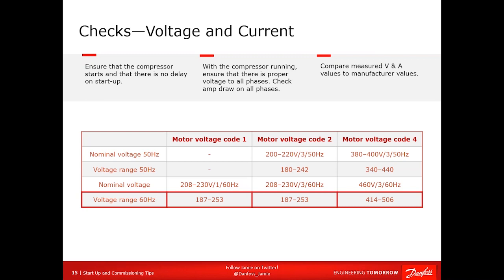So voltage. You have a voltage range and rating. It's in the application guide. That's where this comes from, inside the installation guides as well. And you'll see a range for the voltages. Make sure you check voltage without the compressor running, verify it, because trust me, it would not be the first time you got a compressor that was not the same voltage as the nameplate. It happens, so be very careful with that.